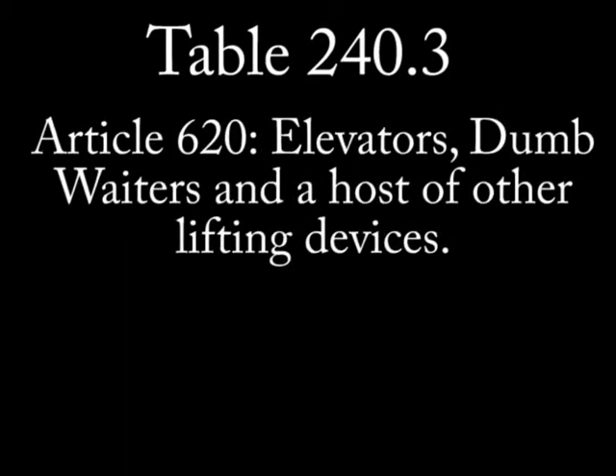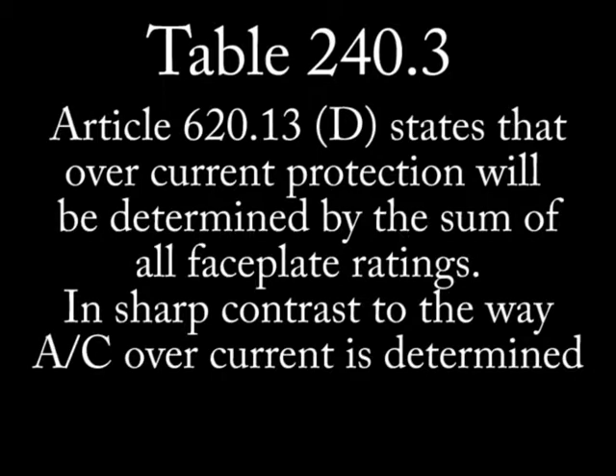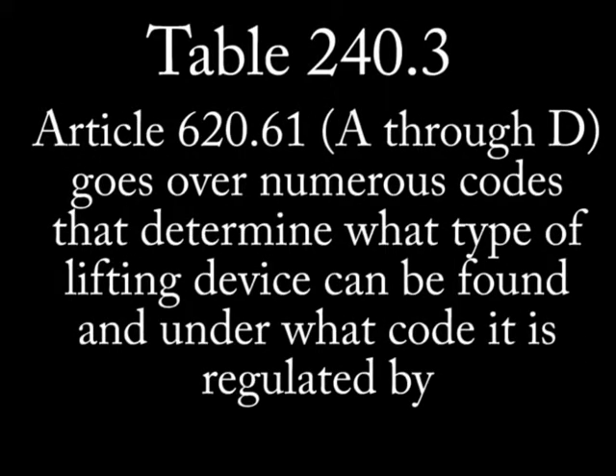Let's look at elevators, dumbwaiters, and other lifting units covered under article 620. There are only two articles directly related to overcurrent protection on this subject. The first is article 620.13 paragraph D, which stipulates that overcurrent protection will be determined by the sum of all faceplate ratings — in sharp contrast to the air conditioning code. The next item is article 620.61 A through D, which points out where you can find specific overcurrent requirements depending on location and type of lifting device.